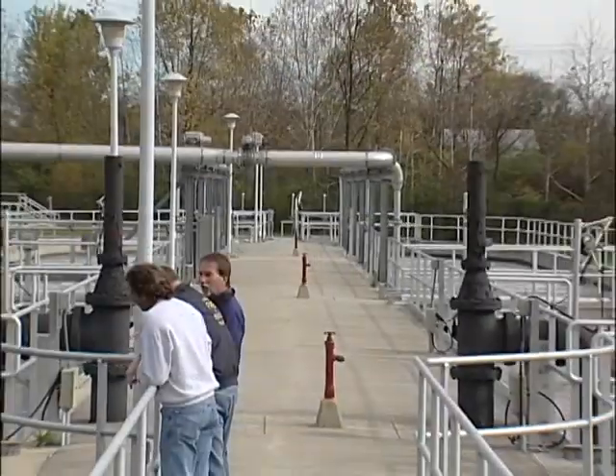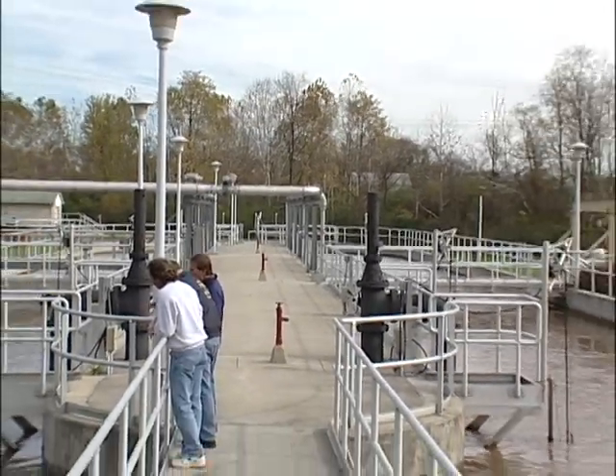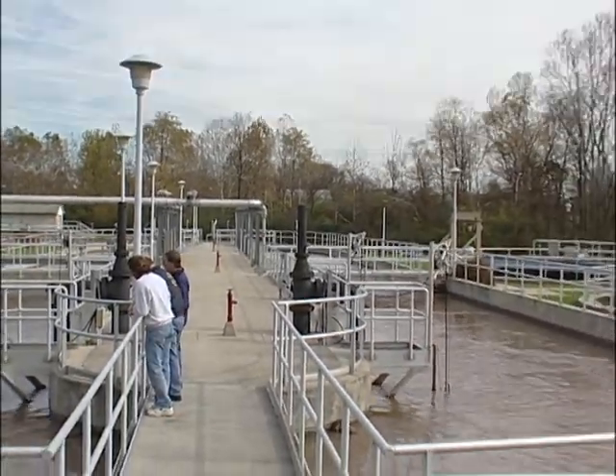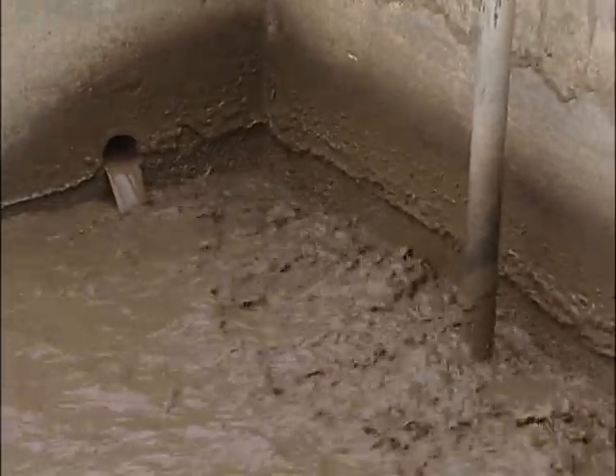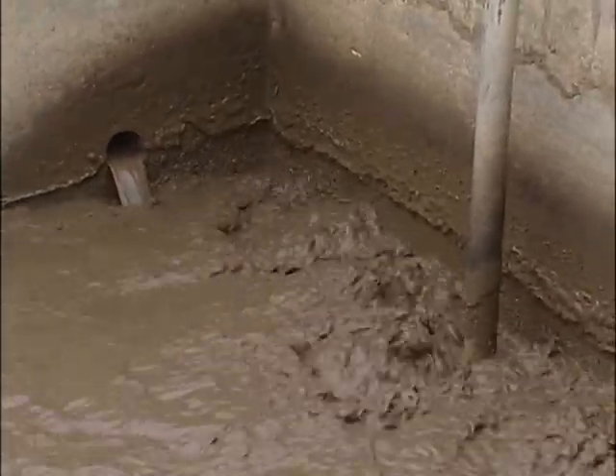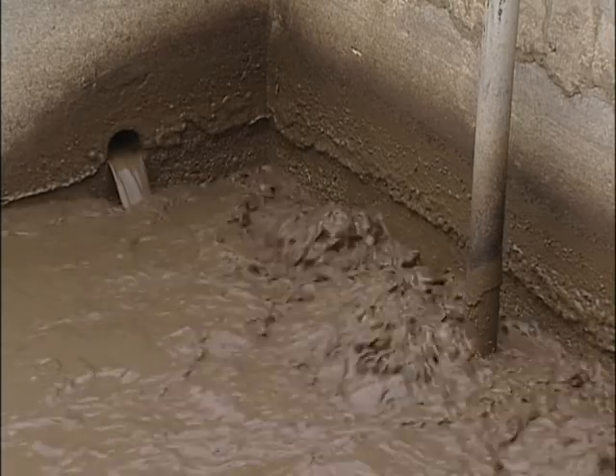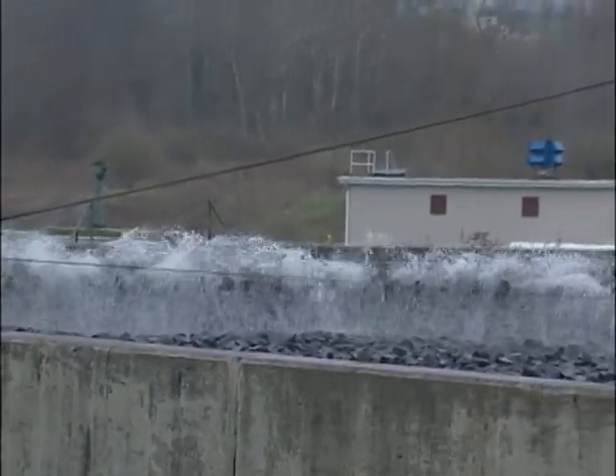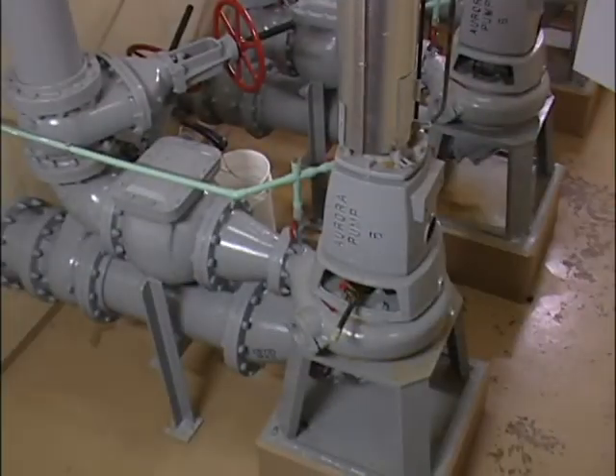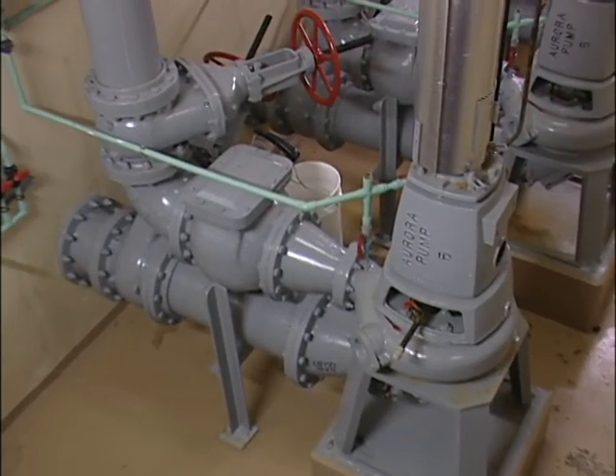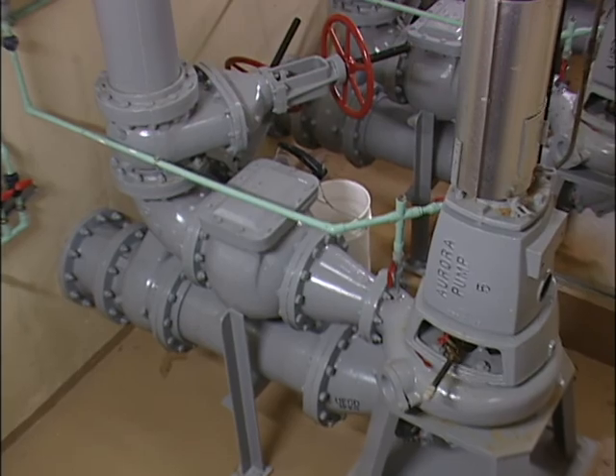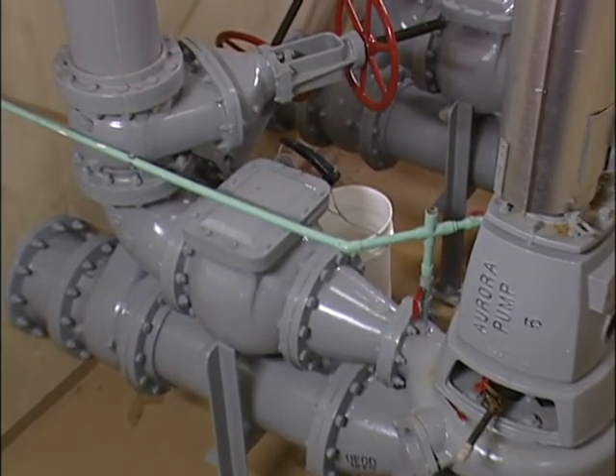For every 10 degrees C rise in temperature, the rate of nitrification doubles, and the MCRT can be reduced in a corresponding fashion. Keeping good records is important. Charting the results of process control work can be very useful. In terms of fixed film facilities, the main process control is the recirculation rate. Increasing the recirculation rate would equate to increasing the MCRT.